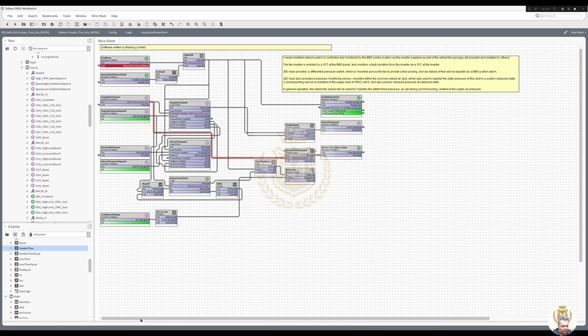And we're not doing anything with this alarm now, are we? Because we don't have an alarm. Man, you can still give it an alarm. Yeah, why not? We can still send an alarm. We're just not sending it to an output. So let's just make a new Boolean writable and extract fan below pressure set point.